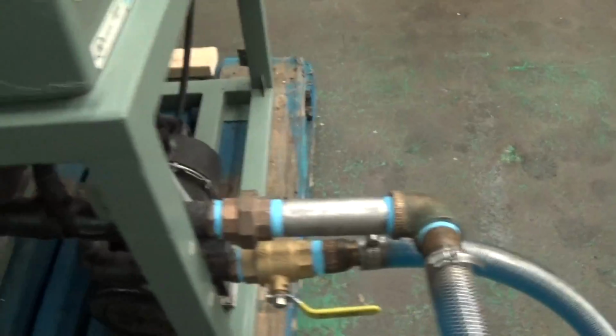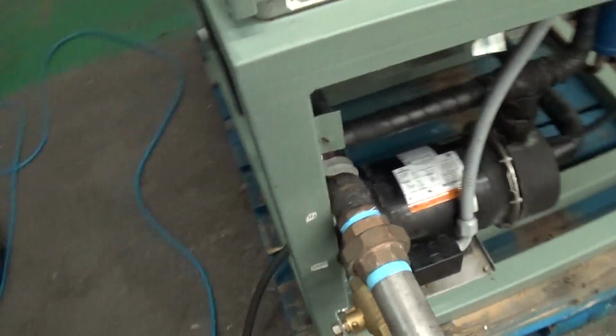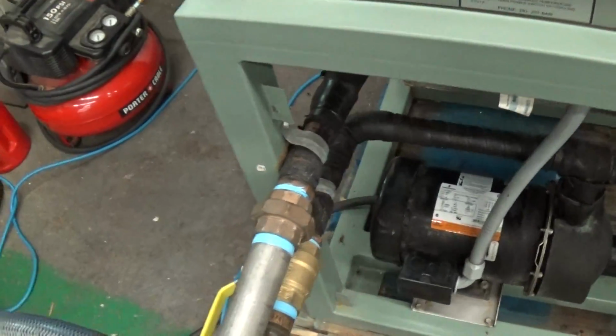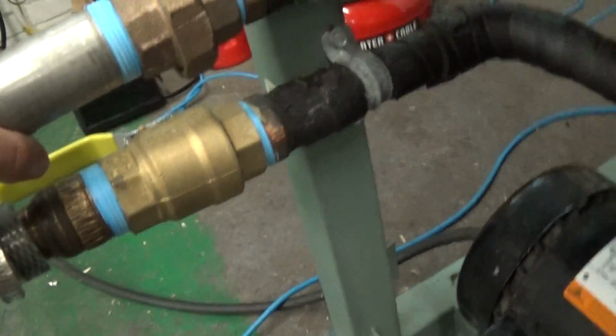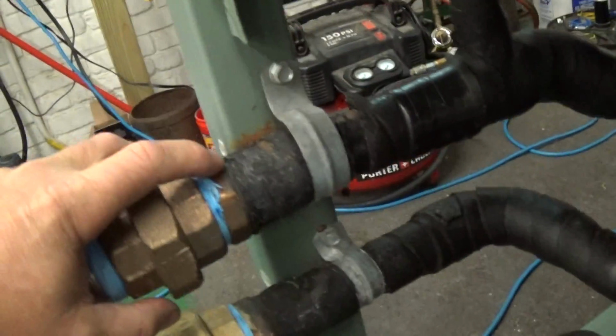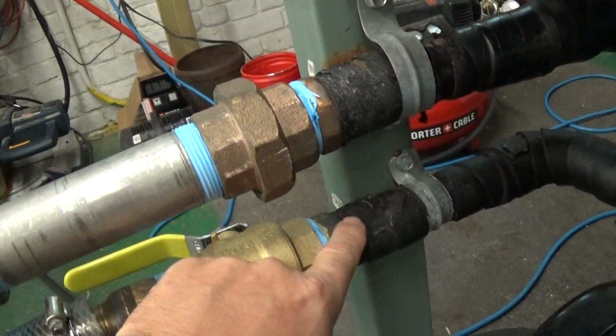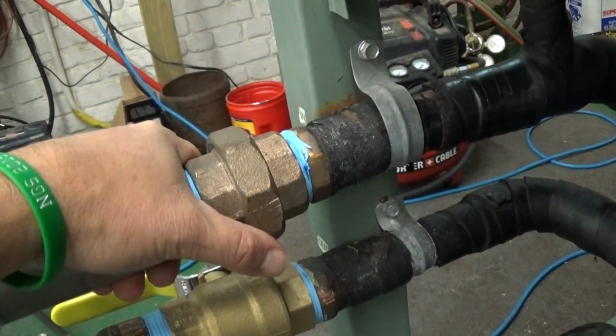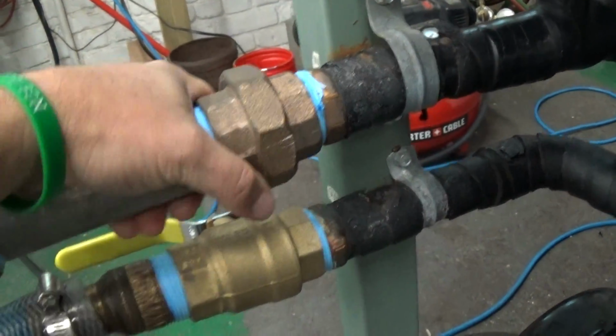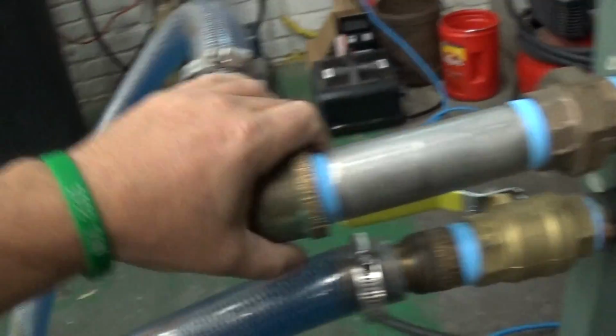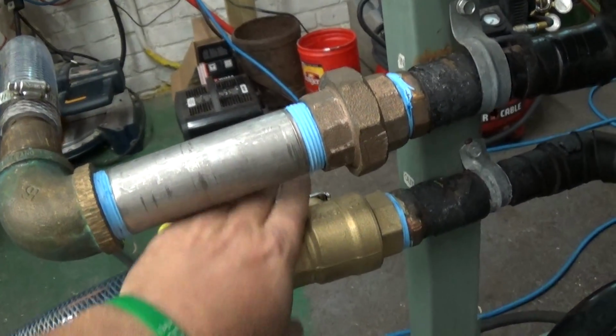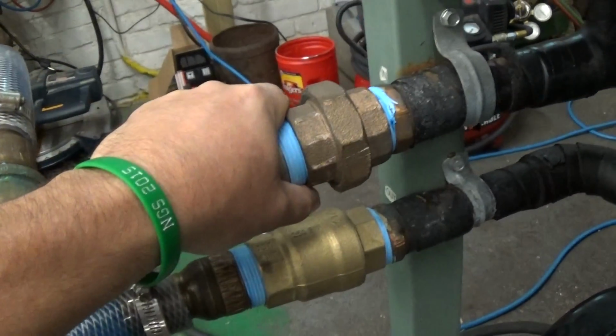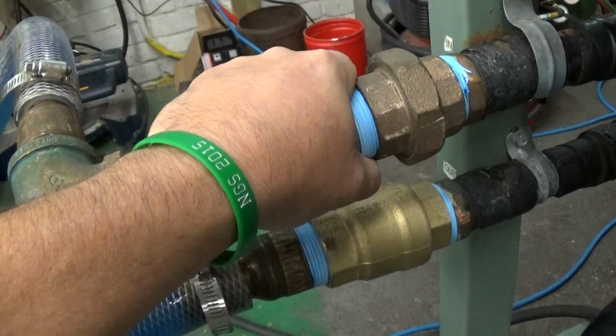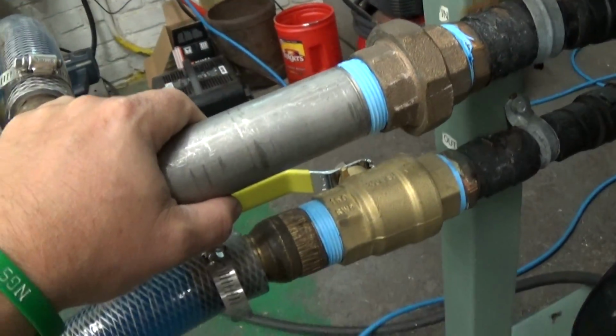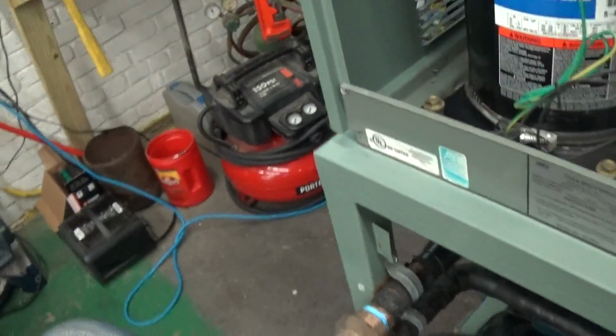The chiller has 1 1/4 inch NPT fittings, and it's going to ship out with just this bushing and this bushing here, which are 1 1/4 male NPT fittings. This is our equipment here just to set up a loop. You should put a shut-off here and a shut-off here prior to going out to your process piping to get to your two immersion coils.